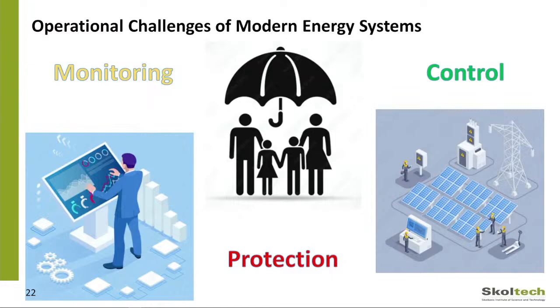We control frequency, voltage, temperature, but the key control loops are voltage control and frequency control. We have different types of frequency control: primary control, 10 seconds; secondary control, 10 minutes; tertiary control, which is economic aspects, maybe a couple of hours. So we must understand the physical process to understand its dynamics and see how we will control the system.